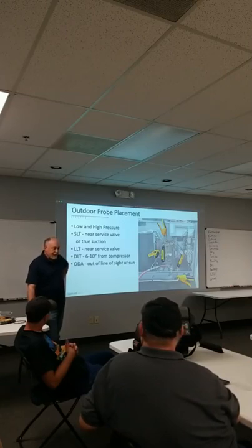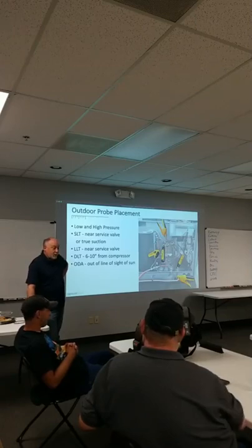And I'll say, yeah. What's the temperature on your liquid line? Well, it's 160 some degrees. Okay, that's not your liquid line. That's coming out of the compressor. No, that's the discharge line. Since when does liquid come out of a compressor?